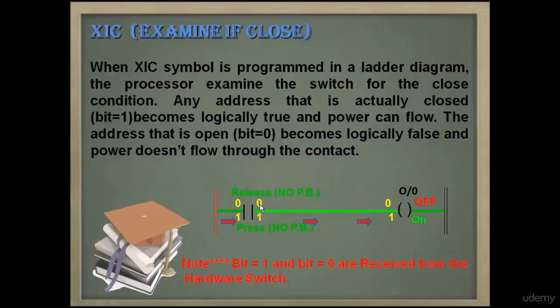If XIC symbol is programmed in a ladder diagram, the processor examines the switch for the close condition. Any address that is actually closed (bit=1) becomes logically true and power can flow. The address that is open (bit=0) becomes logically false and power doesn't flow through the contact.